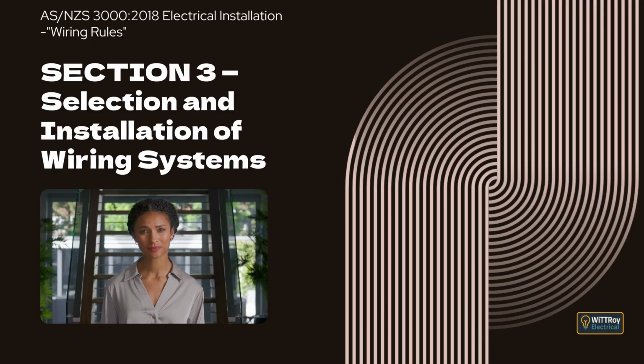That brings us to the end of Section 3. We've now covered the key requirements for wiring systems, including how they are installed, supported, protected, enclosed, run underground, installed overhead, and used for special systems such as safety services and earth sheath return systems. These rules are essential for ensuring wiring systems are safe, durable, and fit for purpose over their entire life. As we move on, the next section will build on this foundation and look at further requirements that apply to specific situations within electrical installations.